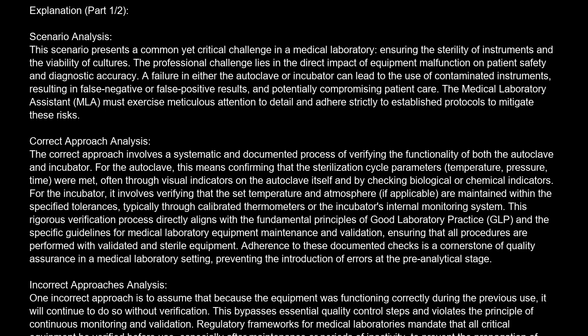Another incorrect approach is to rely solely on the equipment's internal error logs without performing independent verification. While error logs can be informative, they do not guarantee that the equipment is operating within its specified parameters for the current cycle. For instance, an autoclave might not log an error if it reaches the correct temperature, but fails to maintain the correct pressure for the required duration. This approach fails to meet the standard of care expected in a regulated medical laboratory, where independent verification of critical parameters is paramount. This constitutes a regulatory failure by not adhering to established validation protocols.